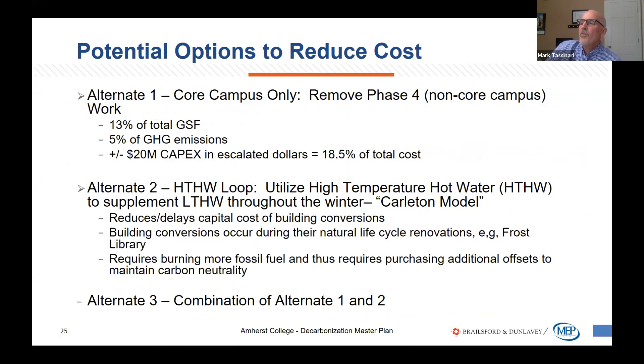The other option we looked at was to segment the hot water loop into a high temperature zone and a low temperature zone. This allows us to defer some of the capital cost of the building conversions necessary for the low temperature water to a future time, when those buildings would normally be up for renovation through programmatic changes or just end of useful life. Both those options looked pretty good to us, so we created a third option...